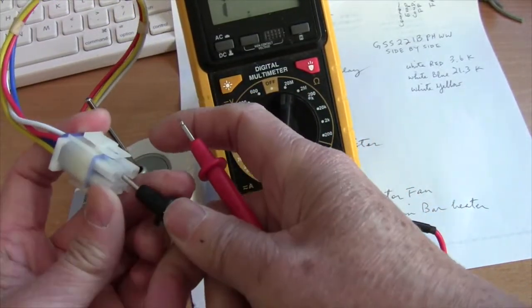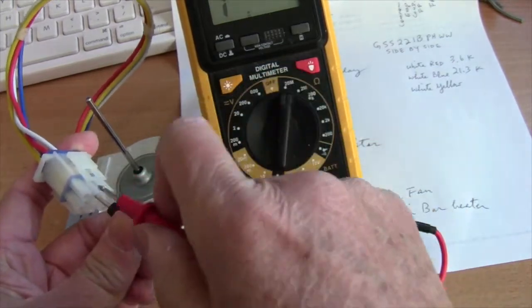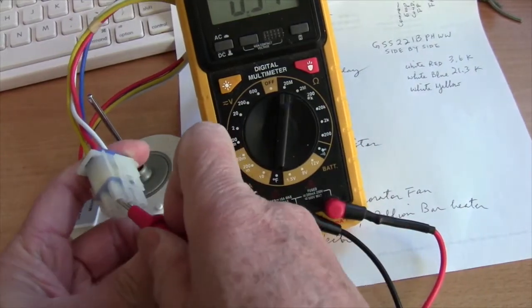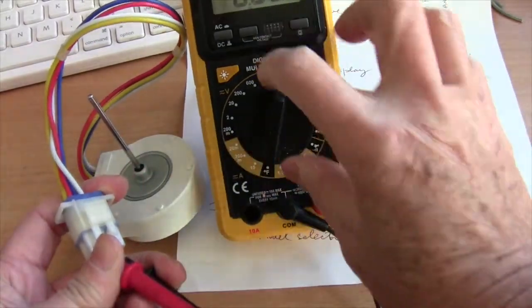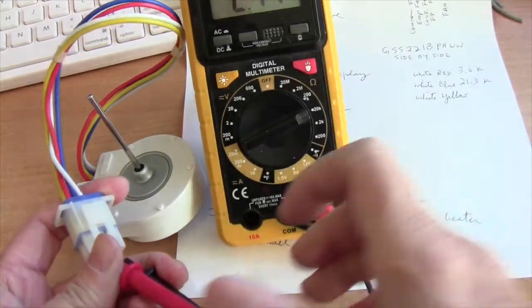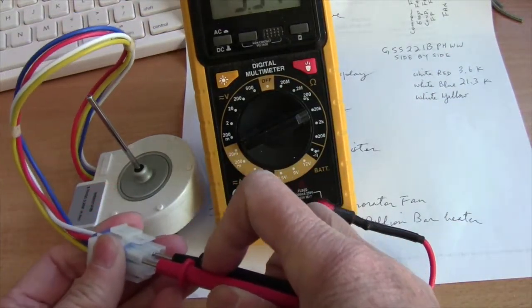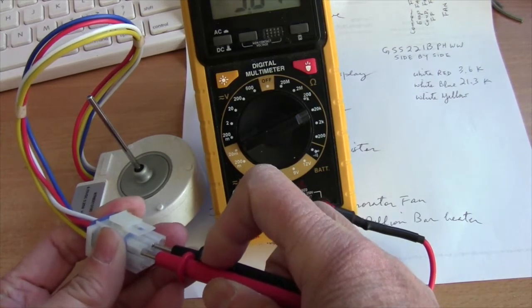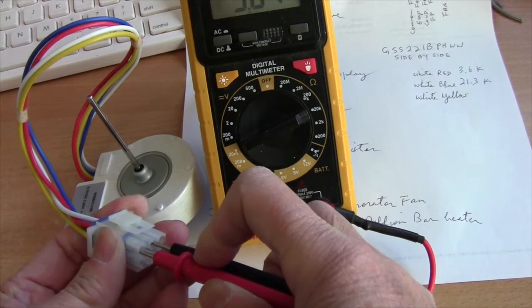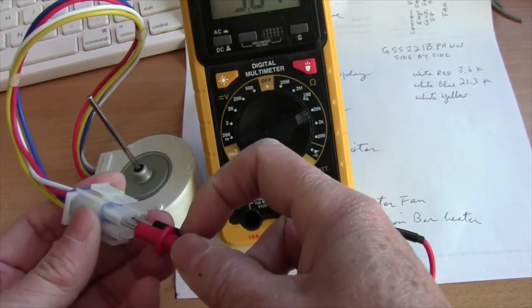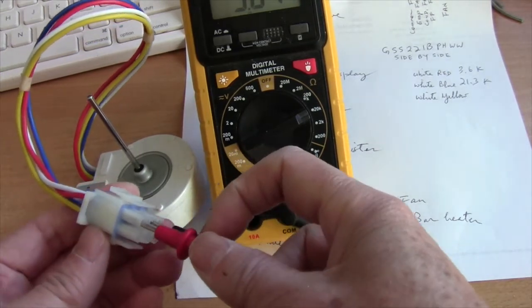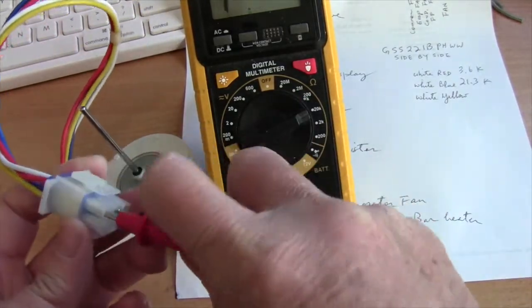And the red wire here is the high speed. So let me just set it. I have done this already, but I'll just show you. So the white and the red wire is about 3.6K. And the lower the resistance, the higher speed the fan will run. So that's the red and the white.